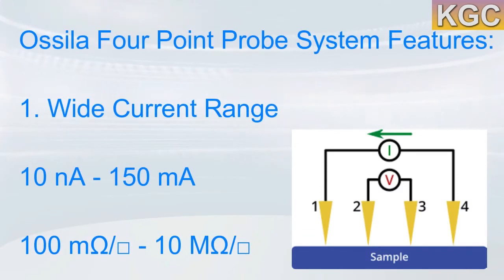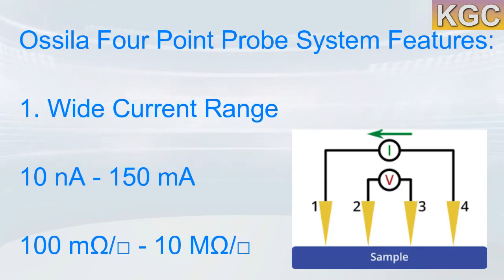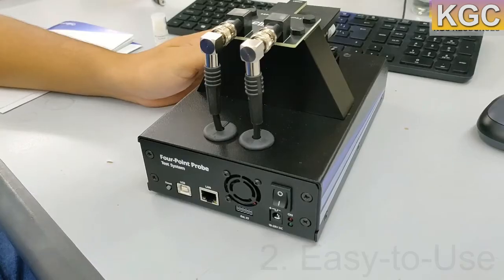Features. 1. Wide current range. The 4-point probe is capable of delivering currents between 10 nanoampers and 150 milliampers, and can measure voltages from as low as 100 microvolts up to 10 volts. The system can measure sheet resistances in the range of 100 milliohms per square to 10 megaohms per square, enabling the characterization of a wide range of materials.